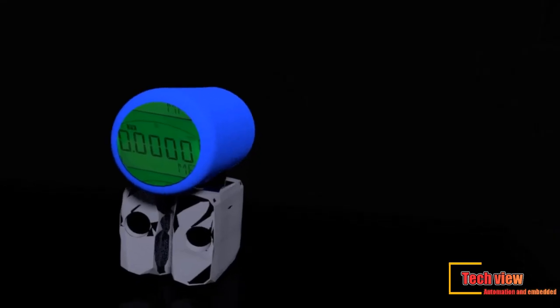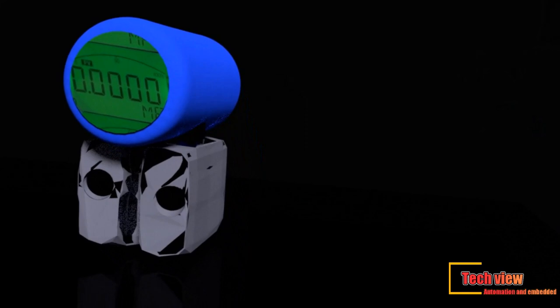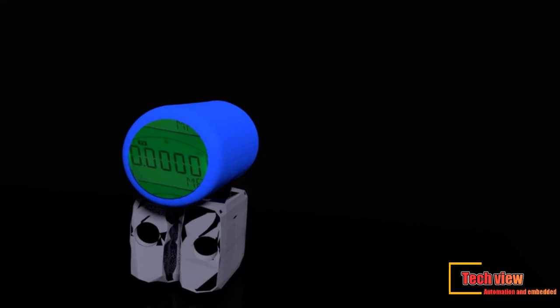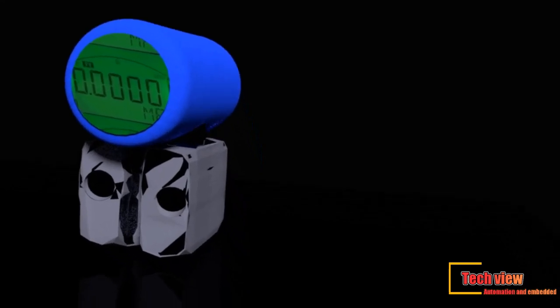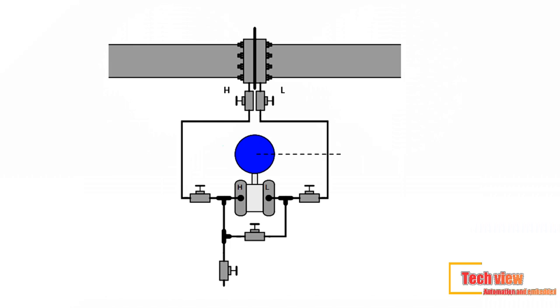Differential pressure flow meters use Bernoulli's equation to measure the flow of fluid in a pipe. They introduce a constriction in the pipe that creates a pressure drop across the flow meter. When the flow increases, more pressure drop is created. Impulse piping routes the upstream and downstream pressures of the flow meter to the transmitter that measures the differential pressure to determine the fluid flow. This technology accounts for about 21% of the world market for flow meters.